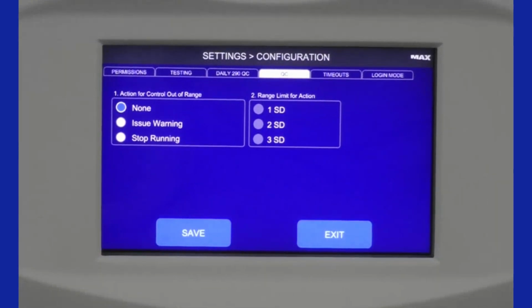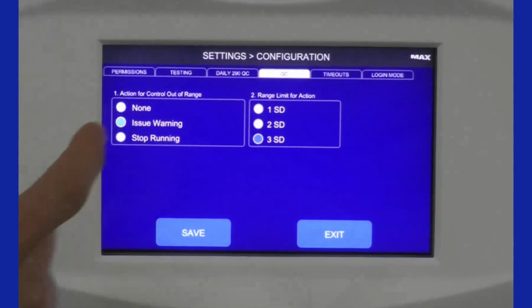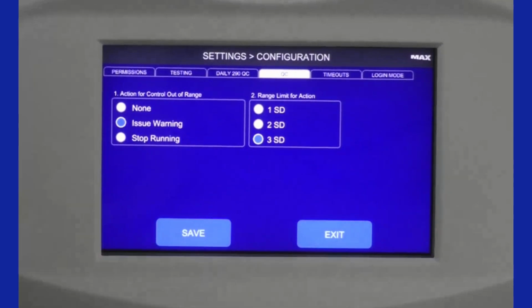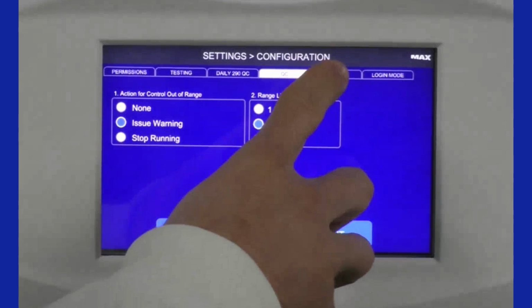So for regular QC operations, most laboratories have a range that's acceptable to them, that their QC result can be outside of the C of A for that lot. So that's what this menu is for. So you get to choose an action that you want the instrument to take if you're outside of the specified range. So let's say you set this to 2 SDs, which is about plus or minus 4 milliosmoles per kilogram of water. And you could have it issue a warning if you're outside of that range, or you could just altogether have the instrument stop running until you're able to successfully bring your QC into spec. So just some things that you can do from that menu.